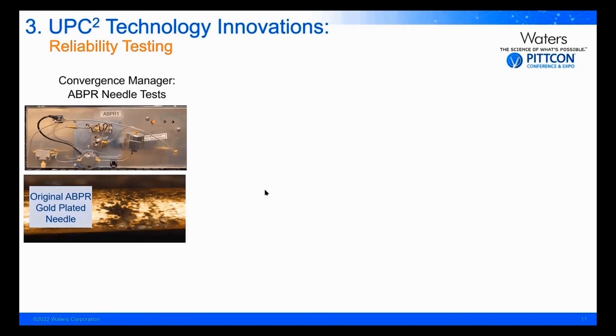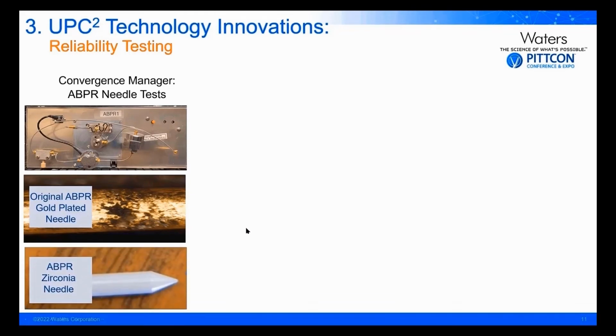The original ABPR needle was gold-plated and started degrading under high CO2 concentrations or high pressures. So to that effect, we modified the ABPR needle into a zirconium-based needle. This withstood high CO2 concentrations as well as higher pressures without any degradation effect. This was a very important step in the reliability of the Convergence Manager.